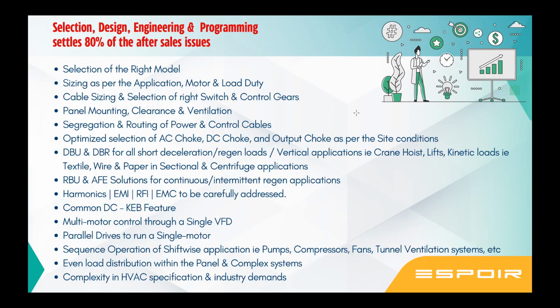Now, in a DOL, it is going to draw 6.5 to 7 times the rated current. 6.5 to 7 times rated current is going to be an overload for a VFD, and the VFD will trip on output motor overload. And it is going to create a lot of other issues. So on a multi-motor configuration, you need to be very careful. Now, a single motor also works on multiple drives, where the motor size is large and you need to use two different drives to couple the power section and then run it. It is possible, but it is generally done at the OEM level. Two parallel power sections are merged and a single control system is given. So that is paralleling of drives. You need to filter. There are a lot of aspects to paralleling of a drive.